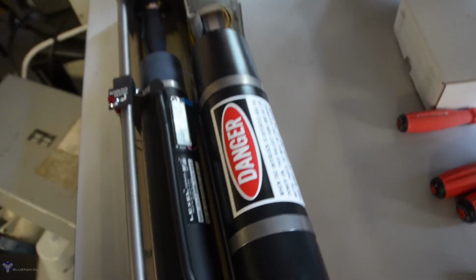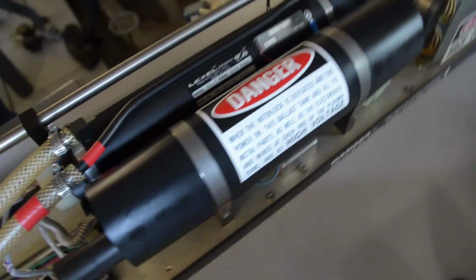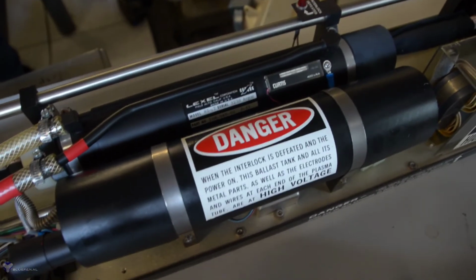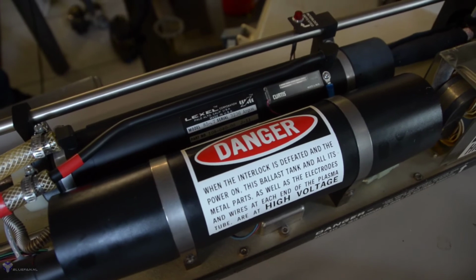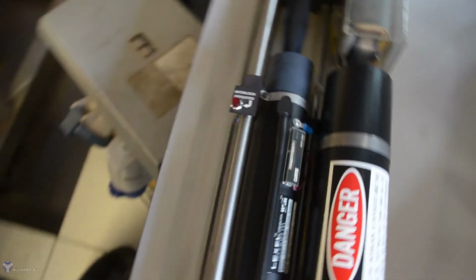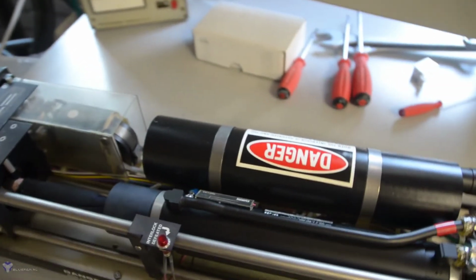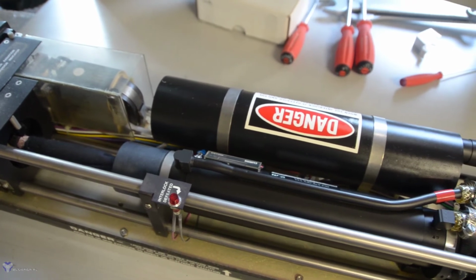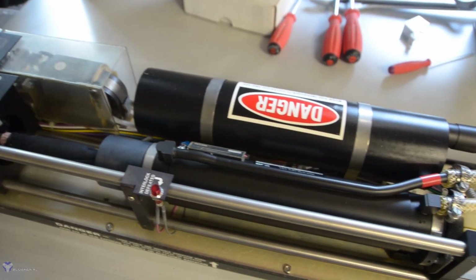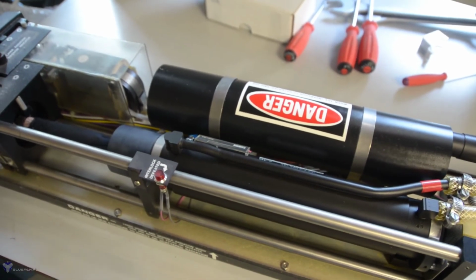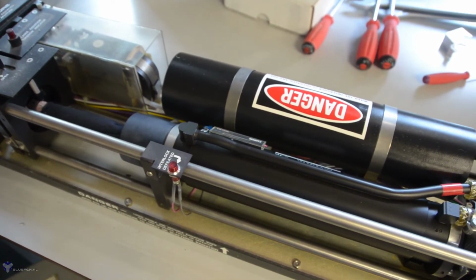Now, there's also a huge warning sign on this tank on the right, which tells you that basically all of it is on high voltage during operation. So not something you want to touch. I think that was the reservoir tank, basically to keep the argon pressure quite stable, because argon can be buried into the walls of the tube, and I think a tank like that can keep the argon pressure more stable during the lifetime of the tube.